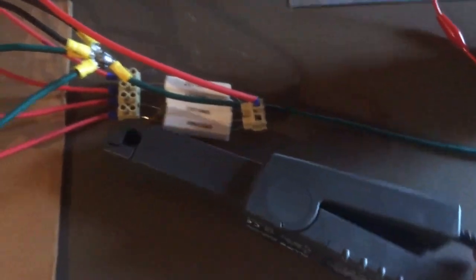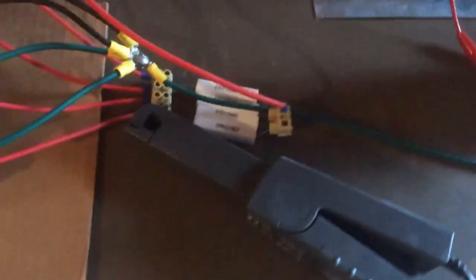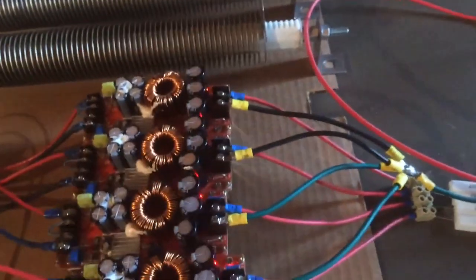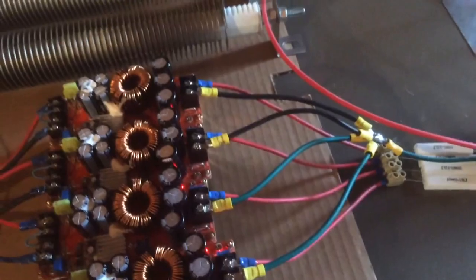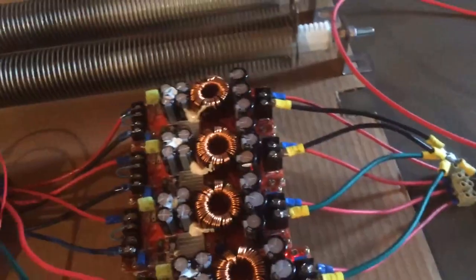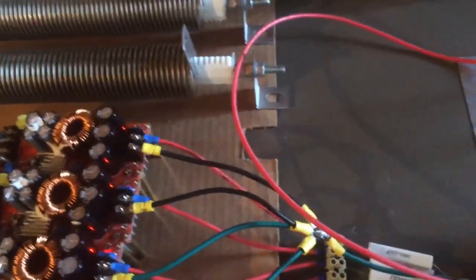So we're gonna go ahead and I'm gonna use my current probe here and we're gonna check each of the outputs now this is on 10 millivolts equal to 1 amp, so you got to move a few zeros we'll do that for you as we go.